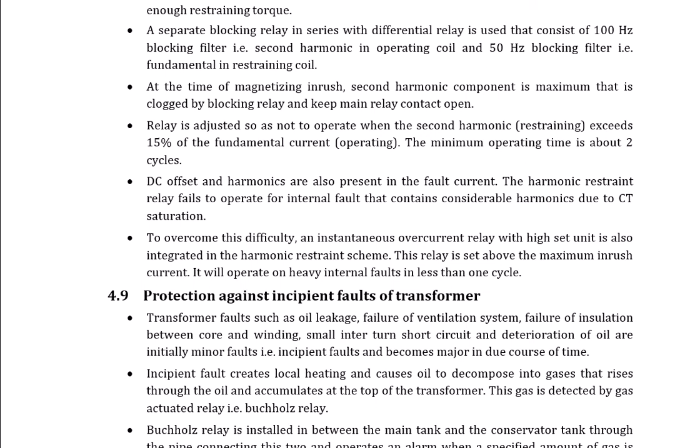saturation. To overcome this difficulty, an instantaneous overcurrent relay with a high set unit is also integrated in the harmonic restraint scheme. This relay is set above the maximum inrush current. It will operate on heavy internal faults in less than 1 cycle. Okay, so we use an overcurrent relay in conjunction with this restraint protection.